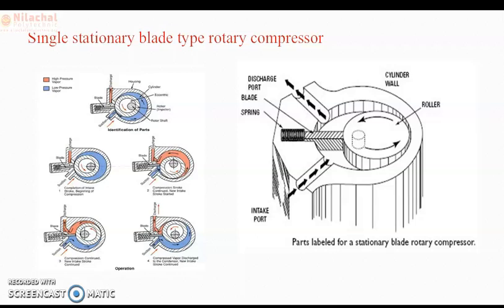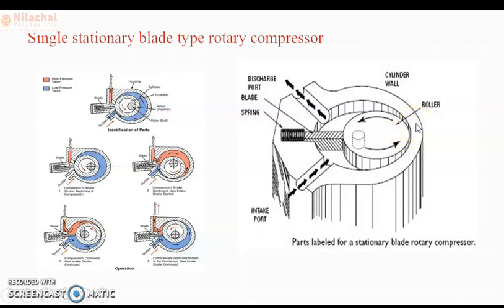Since the blade separates the suction and the discharge ports, it is sometimes called the sealing blade, because it separates the high pressure side and the low pressure side — the suction side is the low pressure side and the delivery side is the high pressure side. When the rotor rotates, the roller also rotates so that it always touches the cylinder wall.